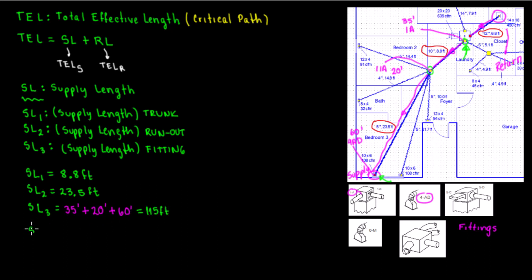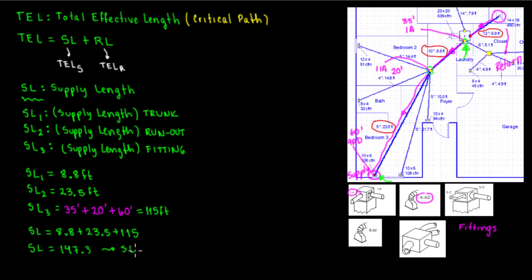The total supply side length — TEL of supply — is equal to 8.8 plus 23.5 plus the equivalent length of the fittings (115 feet), giving us 147.3 feet. Rounding up, the supply side total effective length is 148 feet.